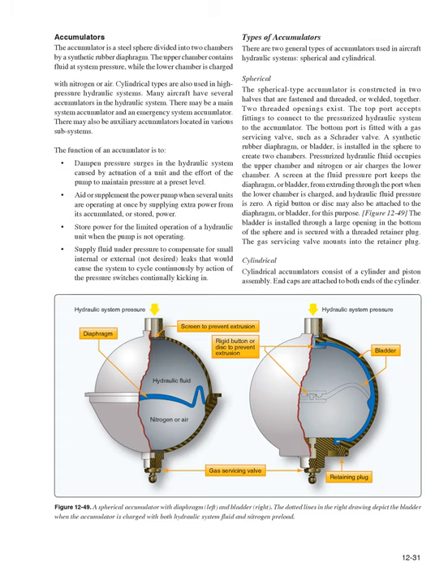Spherical. The spherical type accumulator is constructed in two halves that are fastened and threaded, or welded, together. Two threaded openings exist. The top port accepts fittings to connect the pressurized hydraulic system to the accumulator. The bottom port is fitted with a gas servicing valve, such as a Schrader valve. A synthetic rubber diaphragm, or bladder, is installed in the sphere to create two chambers. Pressurized hydraulic fluid occupies the upper chamber and nitrogen or air charges the lower chamber.